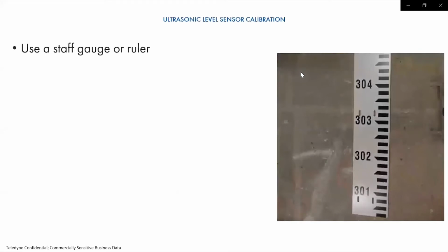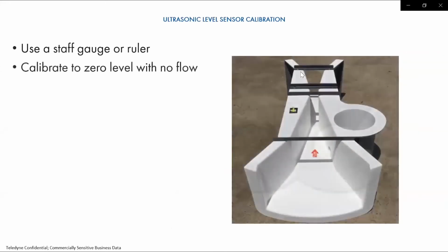Now with the ultrasonic sensors, depending on the flume, a lot of times they will have a staff gauge already built on the side of the flume, which is fantastic. It's a consistent ruler that's going to help you read your level readings. If you can stop the flow, calibrating 0 level is the absolute most accurate way to do that. However, it's not practical or possible in most applications.